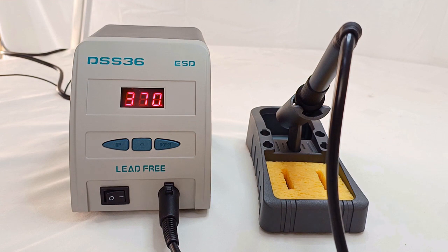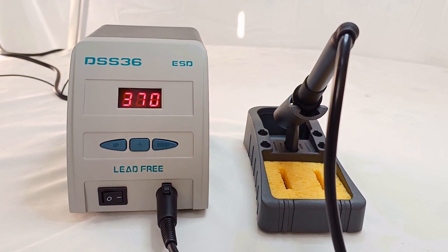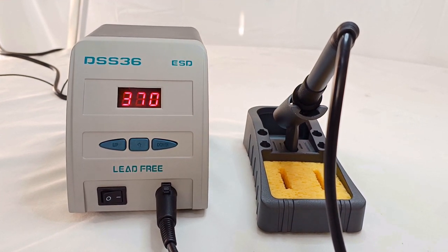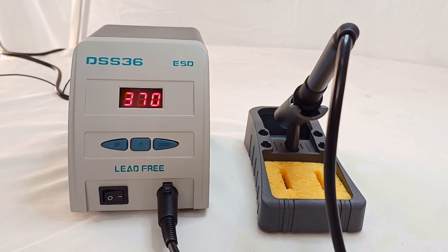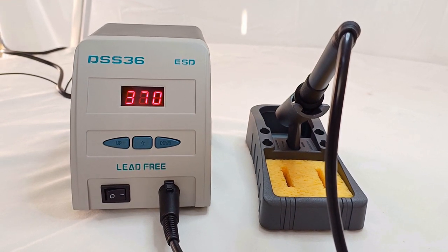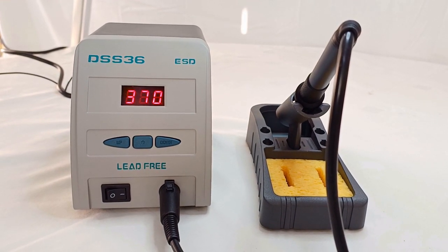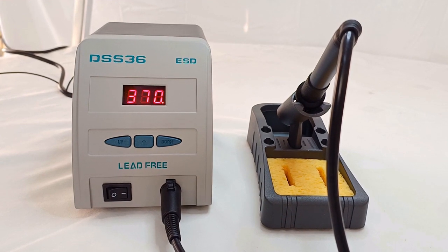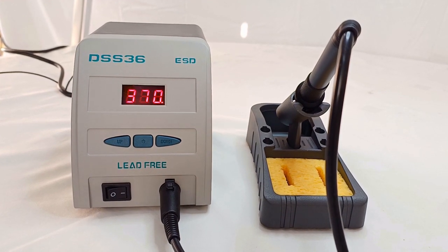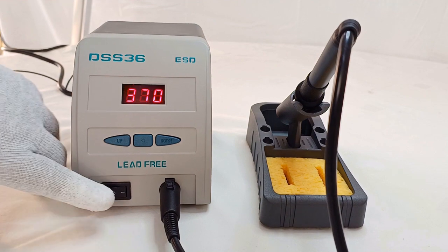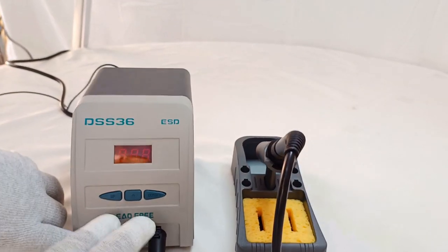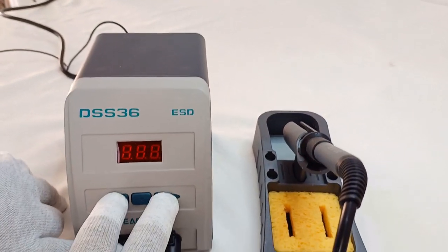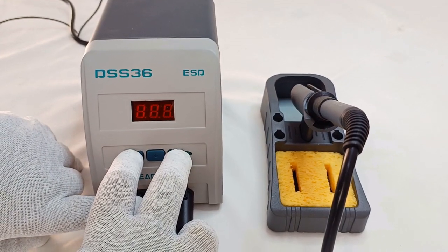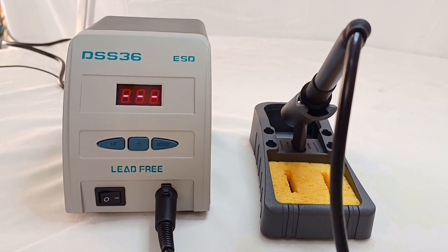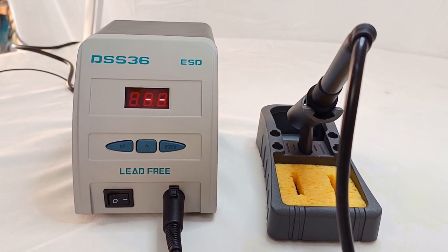See, as you can see, the set temperature is 370 degrees. If we enable the temperature locking feature, then the temperature will be locked at 370 degrees centigrade, and the operator will not be able to change the temperature. Let's see how it is enabled. Just switch the unit off, then press the up and down buttons simultaneously and switch the unit on. As you can see, 3 cursors are flashing on the display itself.